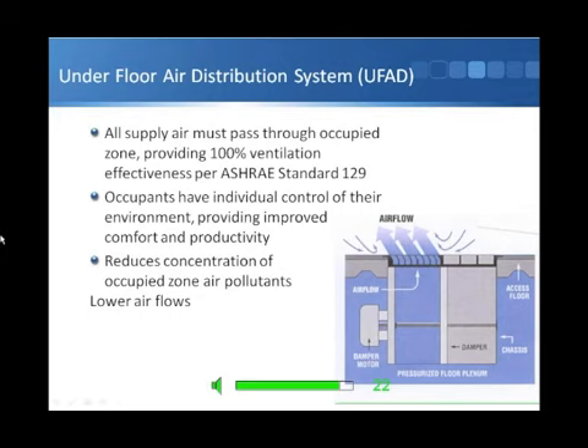So to deal with that, of course, we need to ensure that the conduits are blocked, so we haven't got airflow or air leakage from the space up, and we are actually measuring the actual room temperature. One advance on underfloor air distribution has been the introduction of VAV boxes in the floor. This allows VAV control more locally, and it allows some rooms to be used as seminar rooms or meeting rooms, other rooms as open space office. There's a lot of flexibility there.